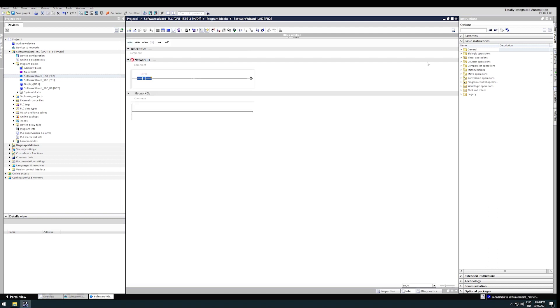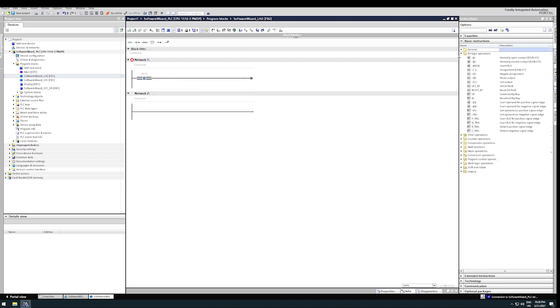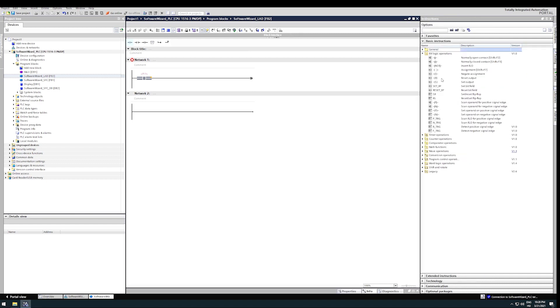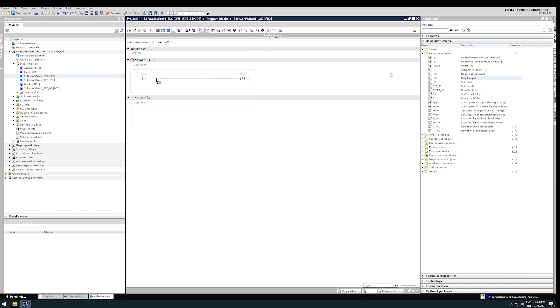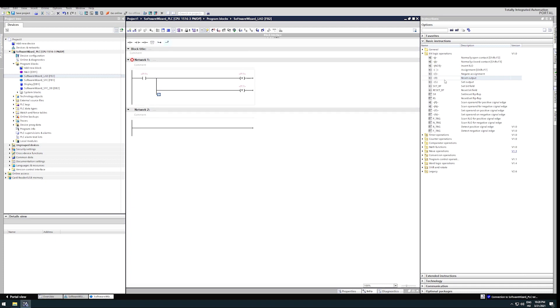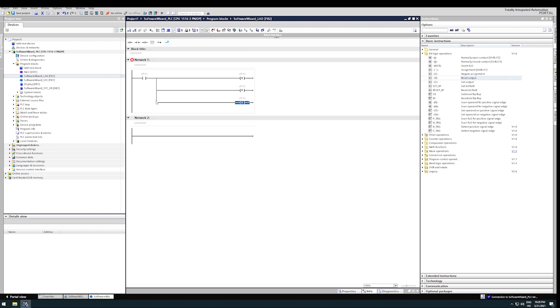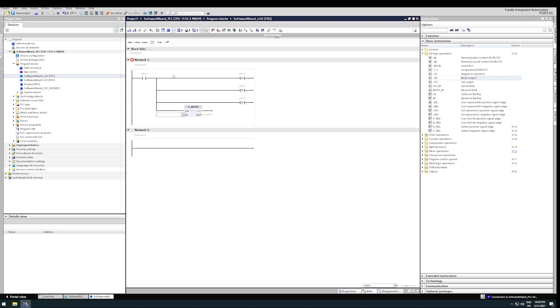You can auto-number your variables by dragging the cell's edge. Network 1 will represent step 1. As we discussed, the actions go to the right side of the rung. With the s-move block you can write values to a string in ladder logic. The transitions also branch down after the step activation bit, because we only want the active steps to be monitored. When the transition's condition is fulfilled, we set the next step and reset the recent step's bit. Let's apply this algorithm to all of the other steps.